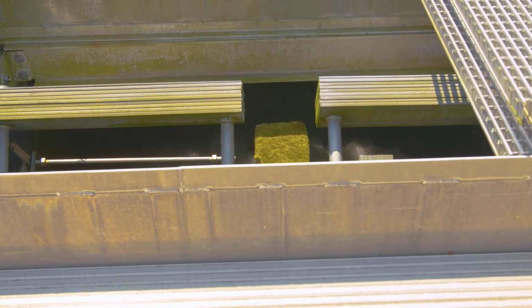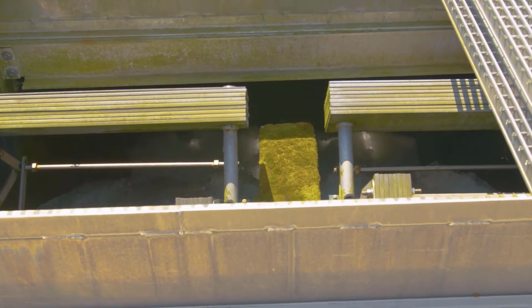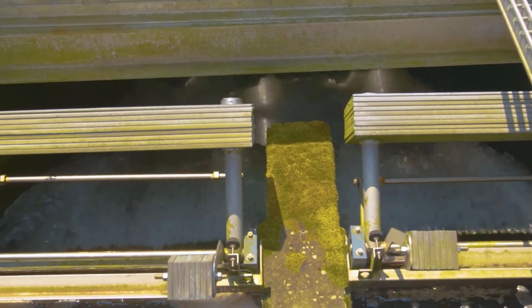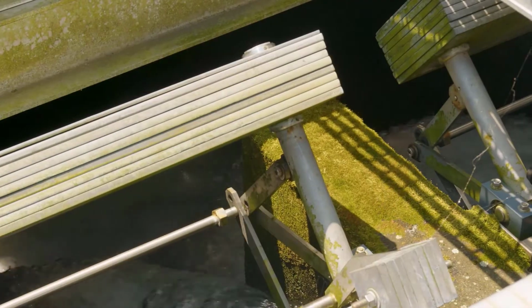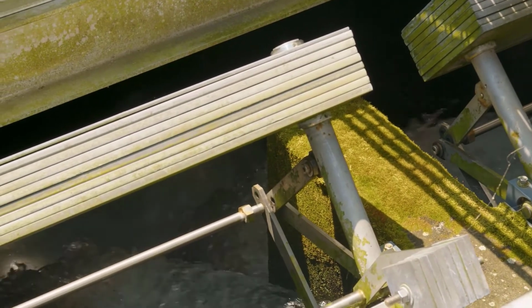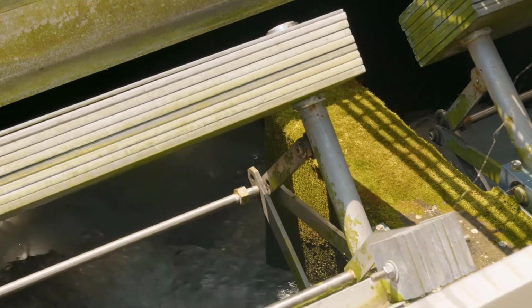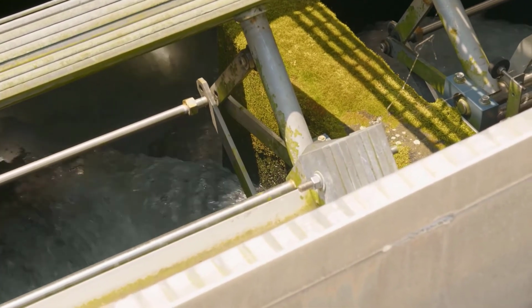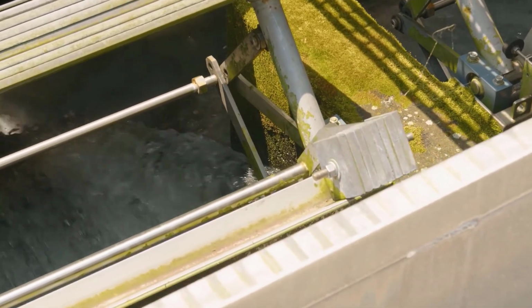In that instance, the top of the water column may not be effectively disinfected, and we may have permit level exceedances. However, that's really rare, and during normal operating conditions, the level control gate at the end of the UV channel helps to maintain the level at the appropriate height so that we're getting adequate disinfection. And at our normal operating conditions, we typically see fecal coliform and enterococci counts in the single digits.